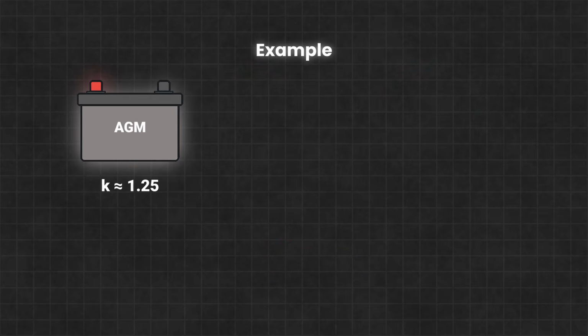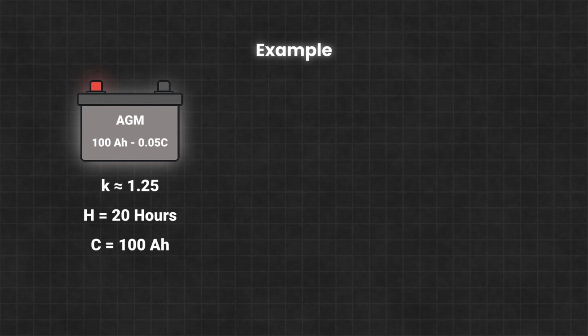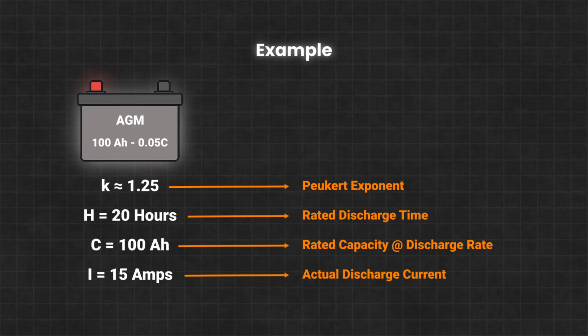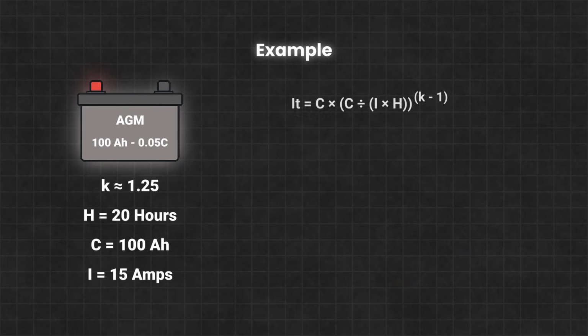So let's say for example you have a 100 amp hour AGM lead acid battery with a 0.05 C rating, equivalent to a rated discharge time of 20 hours. And let's say you plan on discharging the battery at a constant rate of 15 amps. You can estimate the effective capacity like this.